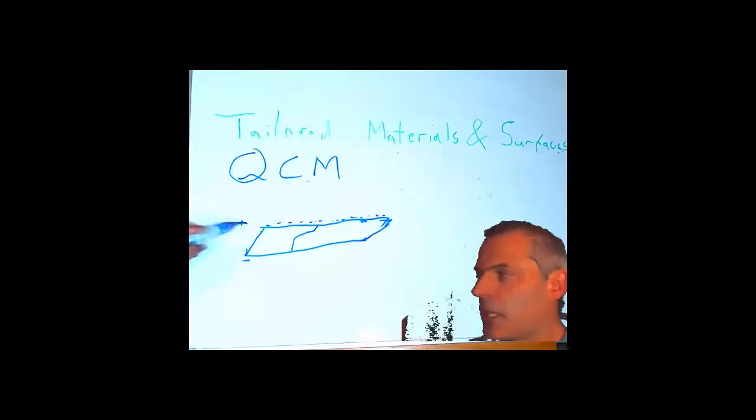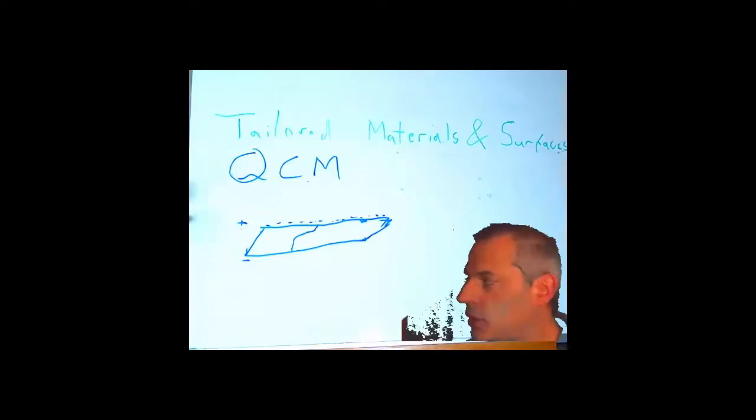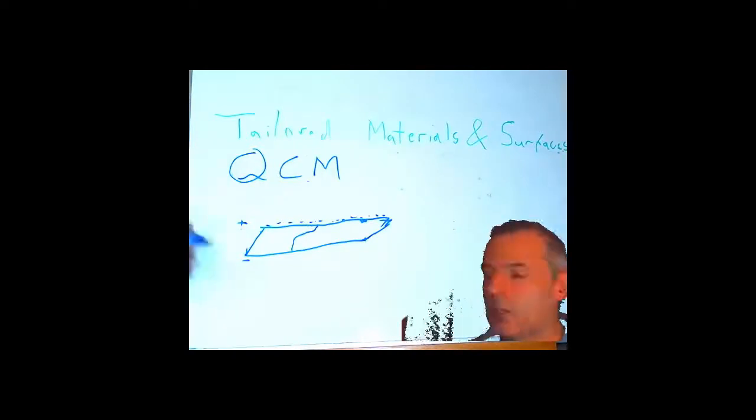We can measure less than a monolayer, less than a full layer of material depositing. These are very often used in coating machines to grossly measure, just find out what's going on, because they will measure up to tens of nanometers of thickness, but they will also measure right down to a sub-monolayer.